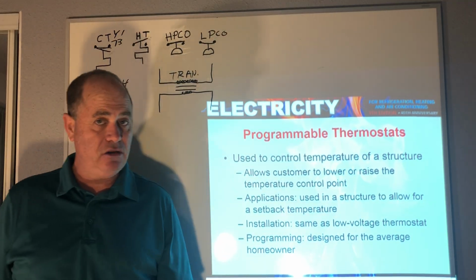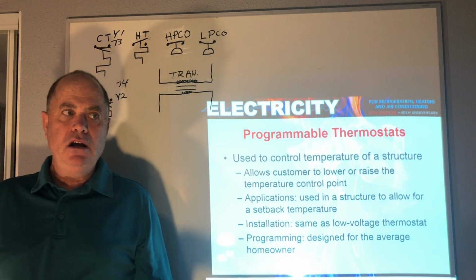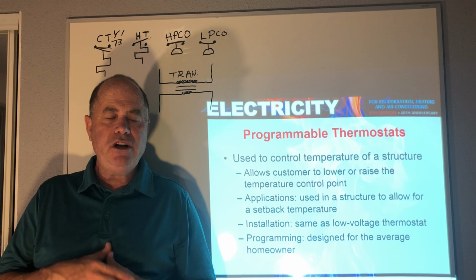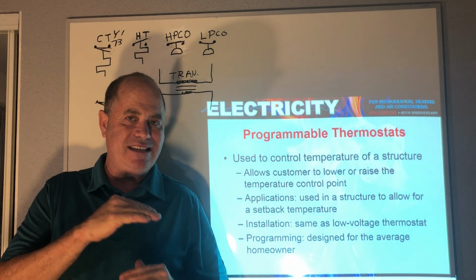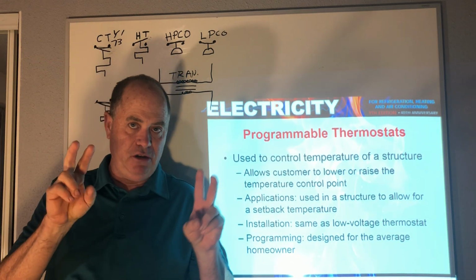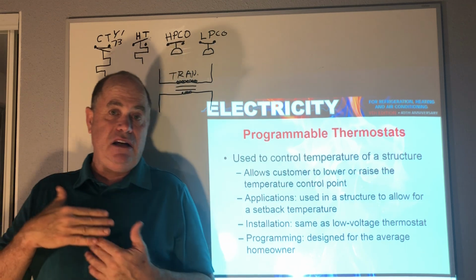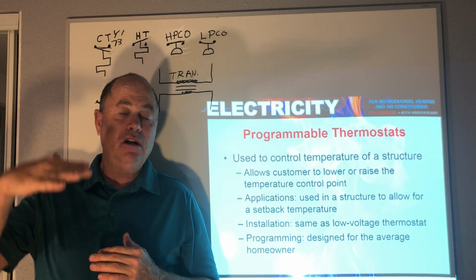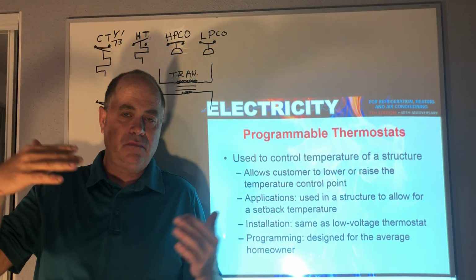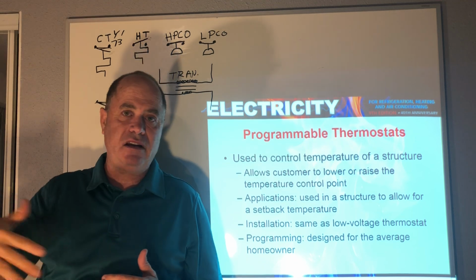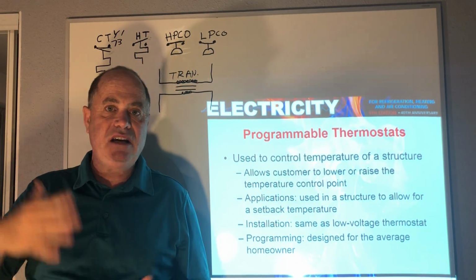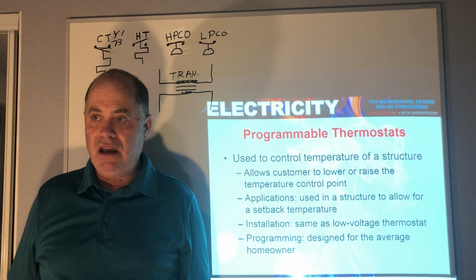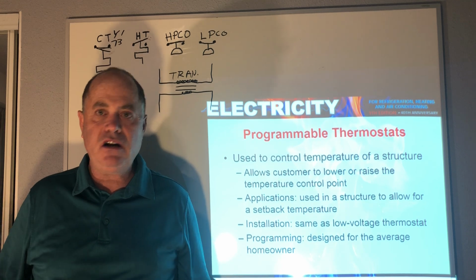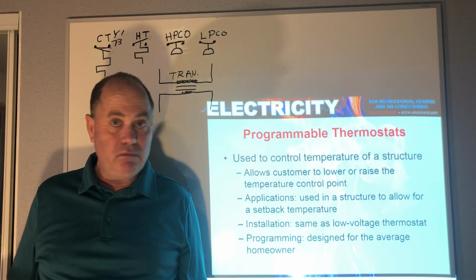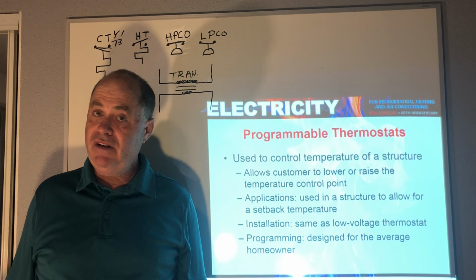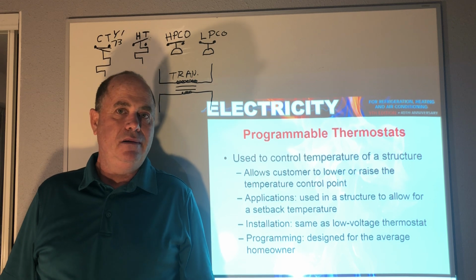And this idea of setback is actually pretty advanced, because even in very complicated large building energy management systems, we don't actually shut the systems on and off. We just rely on that setback so that we don't lose a building. It might be that in the summertime when nobody's there, we put the cooling at 83 or 84 degrees, so the building can never get to 85. Because if a big building gets to 85 degrees, and then somebody says, hey, we need to come in, and we had a massive heat wave over the 4th of July weekend, nobody was here, the building got to be 85, 86, and then people show up on July 5th, even if you run the cooling all out, nobody's going to be comfortable or happy for at least half a day.